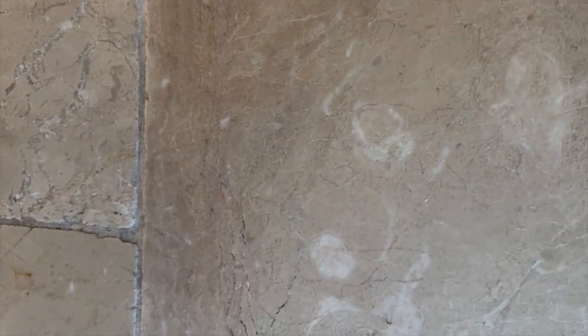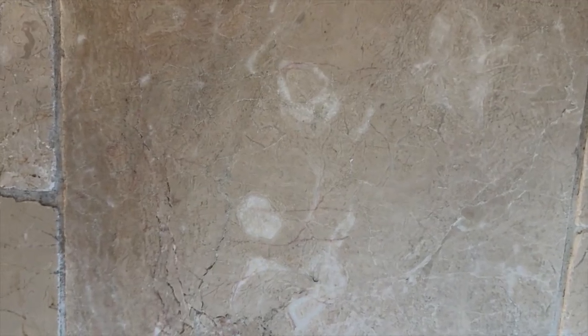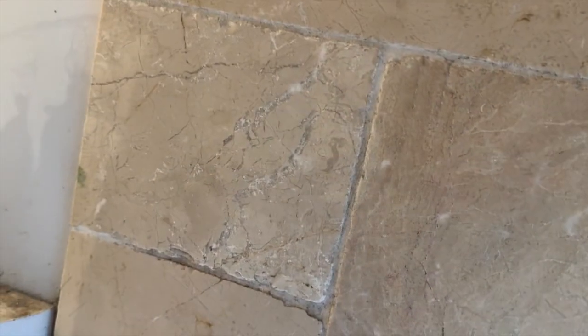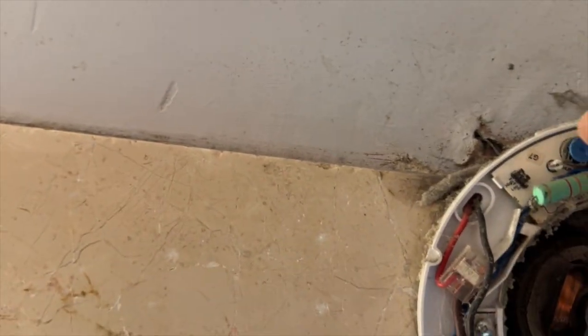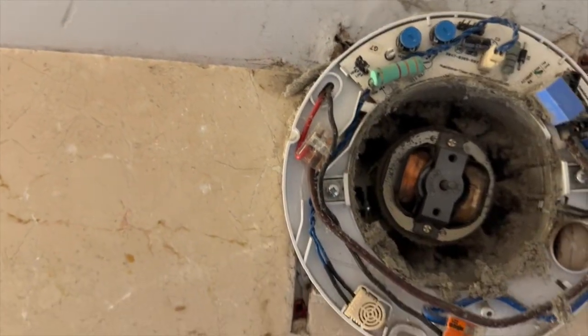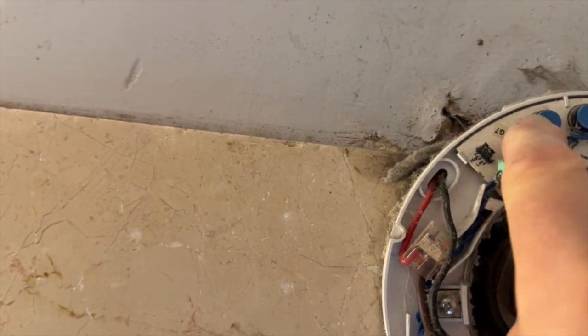It's not working at the moment, so it's relatively humid in here. Feels relatively humid. So if you flip, here we go. It's very blocked up, and an old toothbrush and a vacuum cleaner will get rid of that. I've turned up the timer so that it should now be half an hour, and the humidistat setting should be about 60 there. So that should work better now.